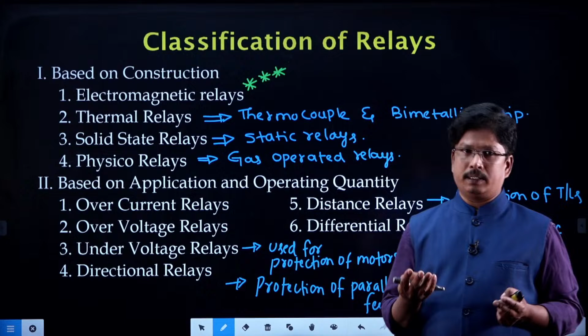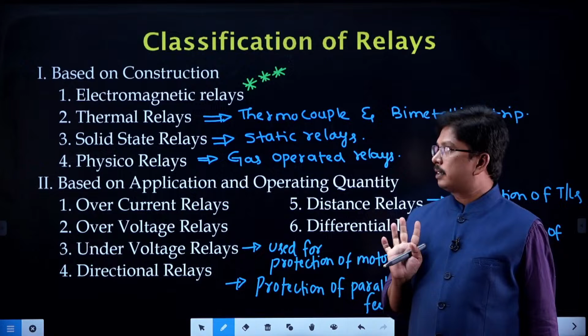Whenever you are writing this, try to remember them by default. Clear, students? In differential relays, we have two types: current differential relay and voltage differential relay. Based on current, the applications are protection of transformer, alternator and bus bar. Based on voltage, we have the Translay relay, used for protection of feeders. Protection of parallel feeders is by directional relays, and protection of feeders by the Translay relay. They are the various types of relays.